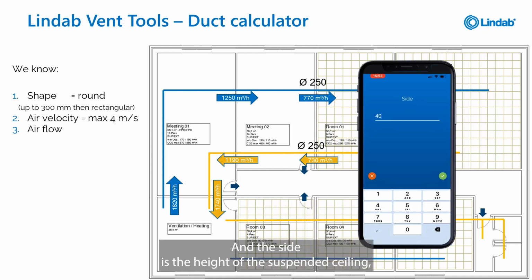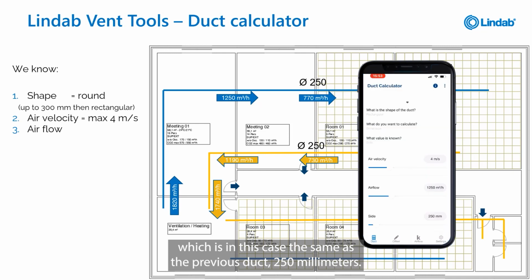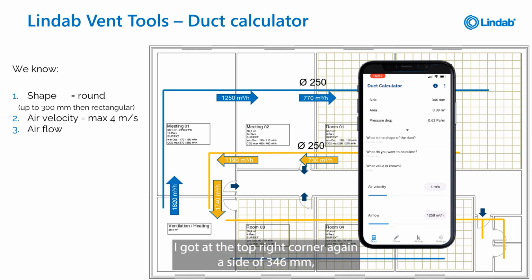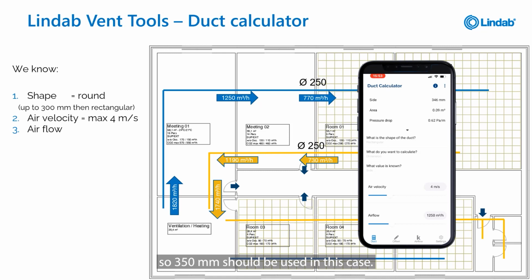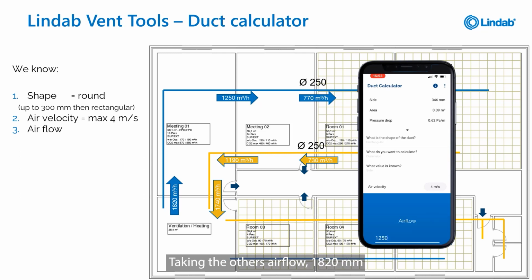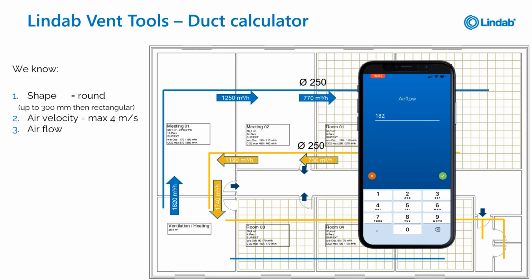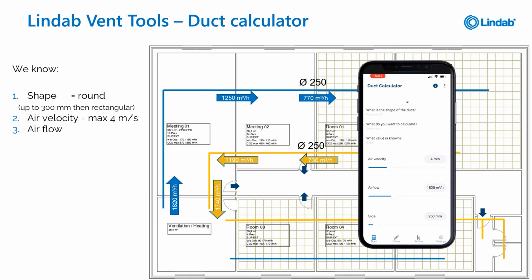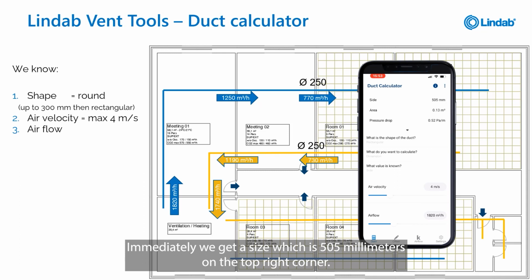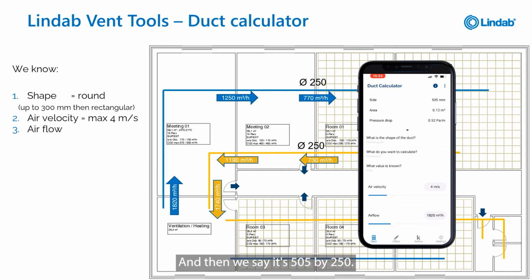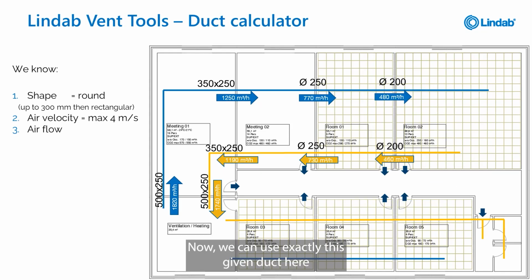And the side is the height of the suspended ceiling, which is in this case the same as the previous duct, 250 millimeters. If I select this now with OK, I get at the top right corner again a side of 346. So 350 should be used in this case. So 350 by 250. Taking the other, airflow 1820. Immediately we get a size which is 505 millimeters on the top right corner, and then we say it's 505 by 250. Now we can use exactly these given ducts here and type them in to the project.